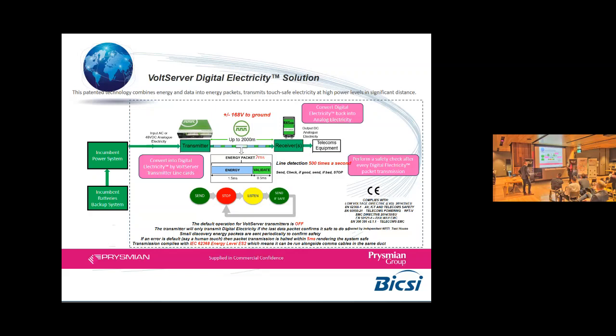So it actually sends a packet of data that has to be received by the receiver every 2 milliseconds. So if anything happens within 2 milliseconds, that system either going to Earth or shorted out in some way, it will actually shut the system down.